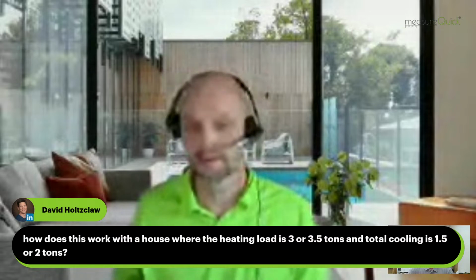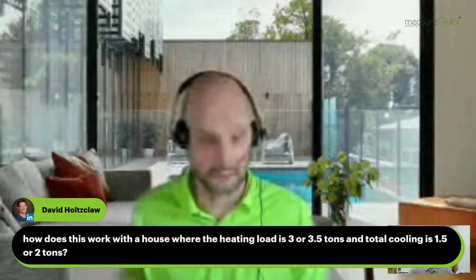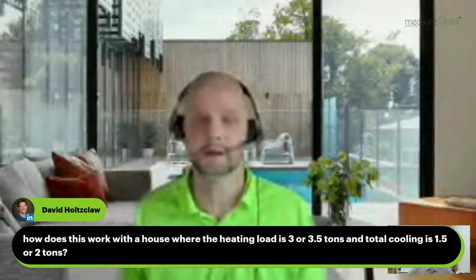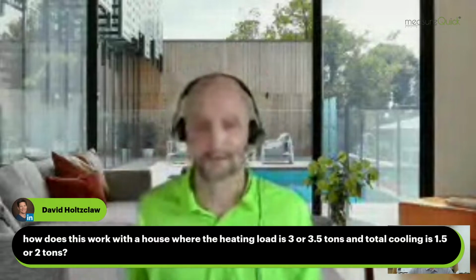This is the perfect example of this ratio of how we can really apply some of these new sizing methodologies, and how we have been doing it for quite a while with these inverter heat pumps. I'm going to show you a slide in a minute here, but you're going to have a turn down that can facilitate. And when I say turn down, that's a minimum cooling capability or minimum heating capability of the heat pump versus the maximum heating capability or maximum cooling capability of the heat pump. If we size towards that heating load, I like to say towards, because sometimes we might not get all the way there, but we try to, like Anthony said, service 100% of the heating load so we don't have to put backup heat strips in.